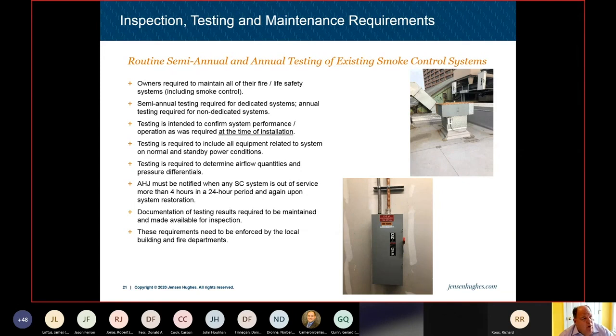So when we're testing these smoke control systems, the testing is intended to confirm the system performance and the operation as required at the time of the installation. It's not trying to meet new code requirements for that smoke control system. It's trying to confirm that it meets the requirements at the time it was originally installed.